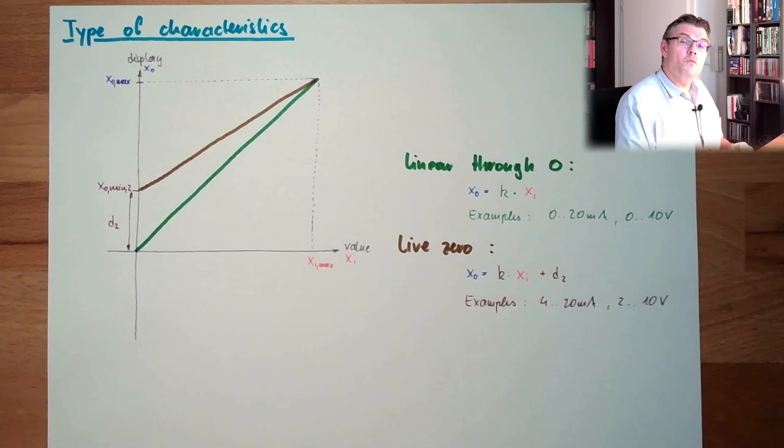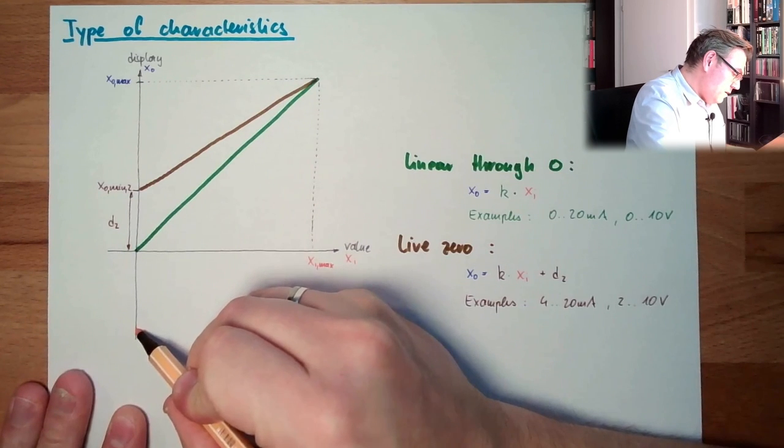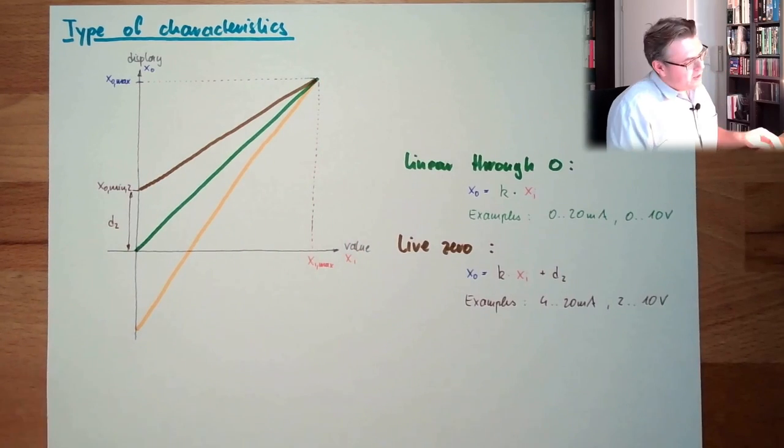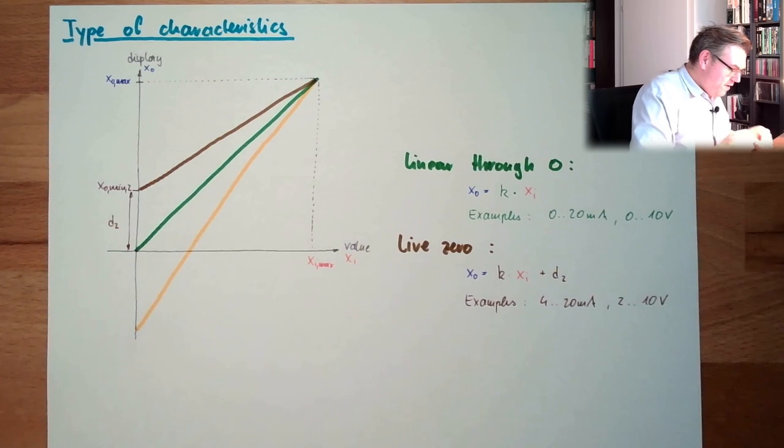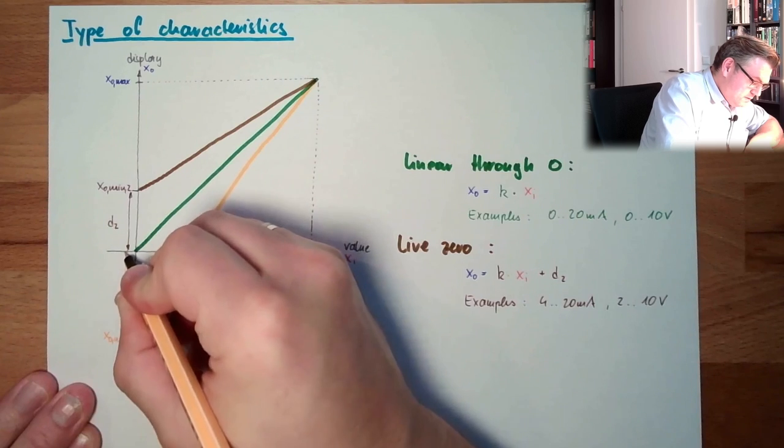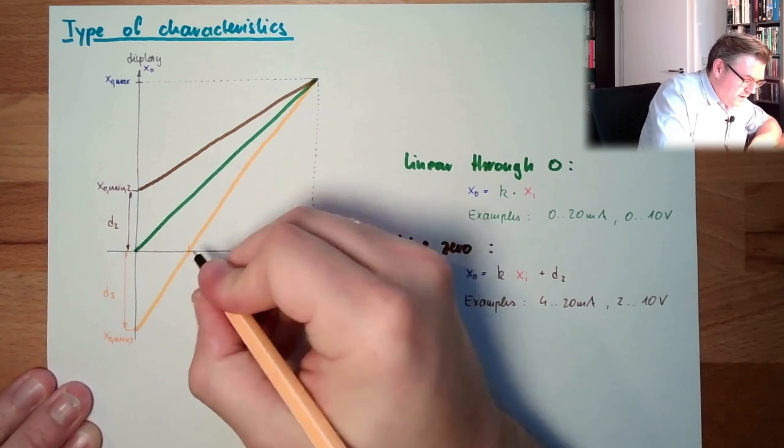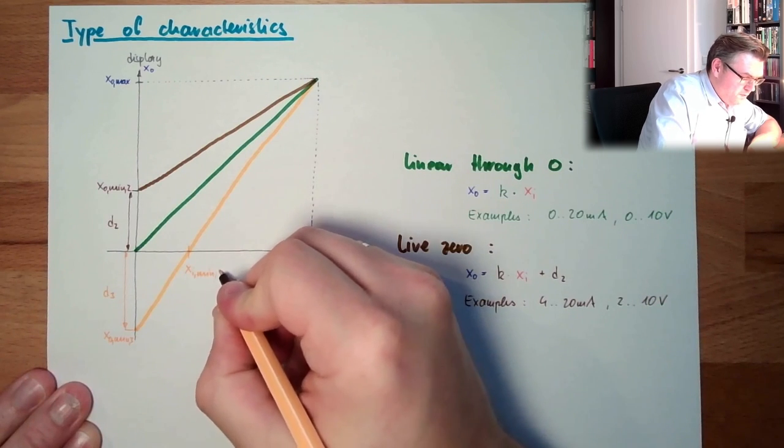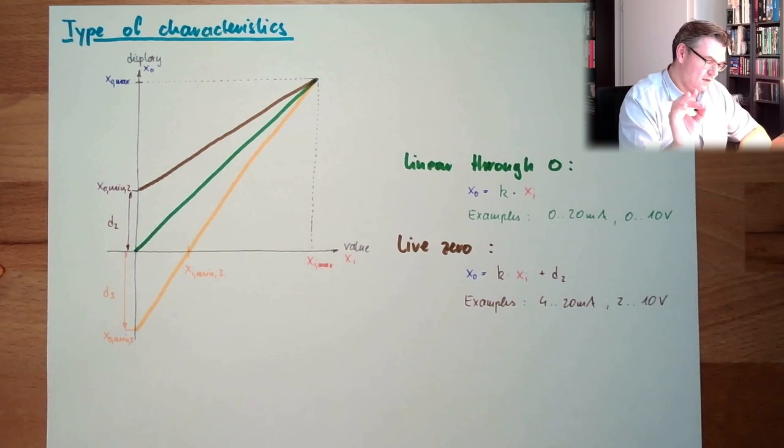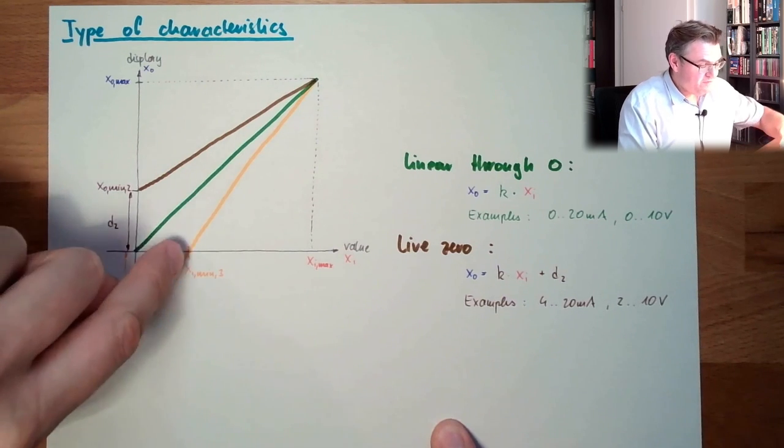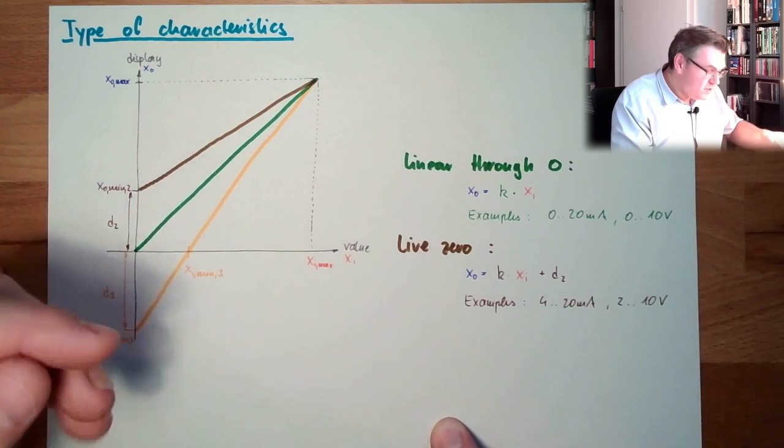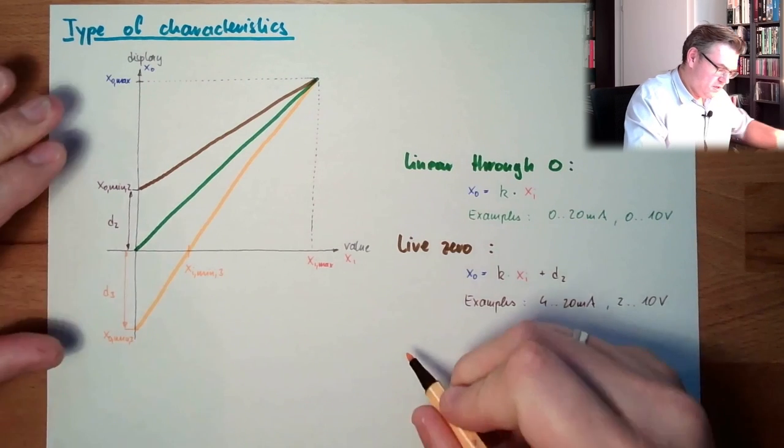And then we have the other way around. We're starting here somewhere, going up. Should also be linear. Here we have XO min 3. This here is D3. And here we have XI min 3. What does this mean? This means, to get an output of this, the value must already have reached this level. So the value is not starting at zero, the value is starting at a minimum. And then we start to display something. This is called suppressed zero. Linear suppressed zero.